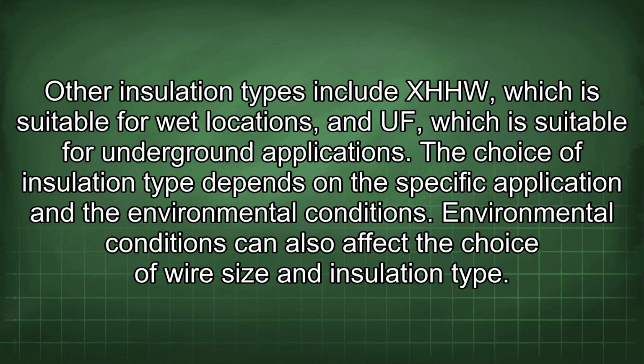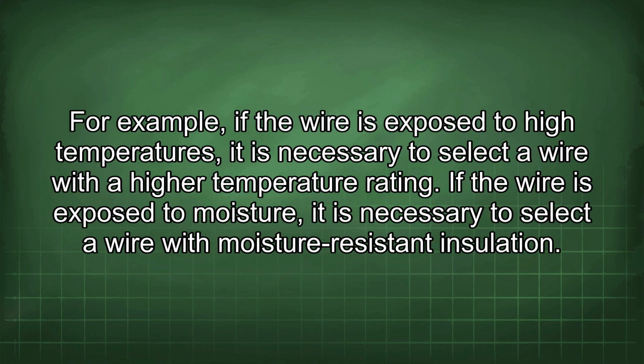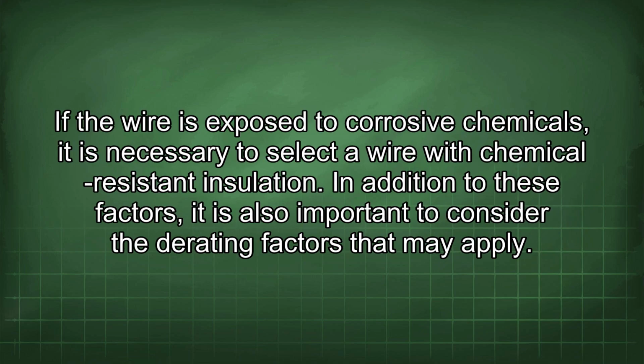Environmental conditions can also affect the choice of wire size and insulation type. For example, if the wire is exposed to high temperatures, it is necessary to select a wire with a high temperature rating. If the wire is exposed to moisture, it is necessary to select a wire with moisture-resistant insulation. If the wire is exposed to corrosive chemicals, it is necessary to select a wire with chemical-resistant insulation.